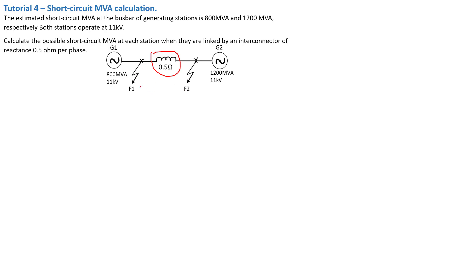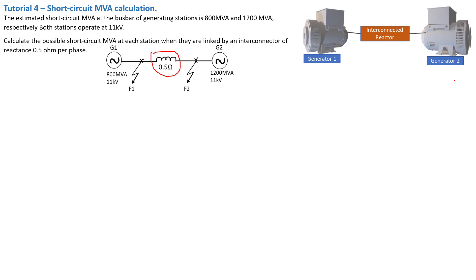Let's move on and find the fault at F1 and F2. Let's see the visual illustrations of our system. We've got generator 1 interconnected with generator 2 by a reactor that is limiting the short circuit current to a safe value. That reactor has an impedance of 0.5 ohm.